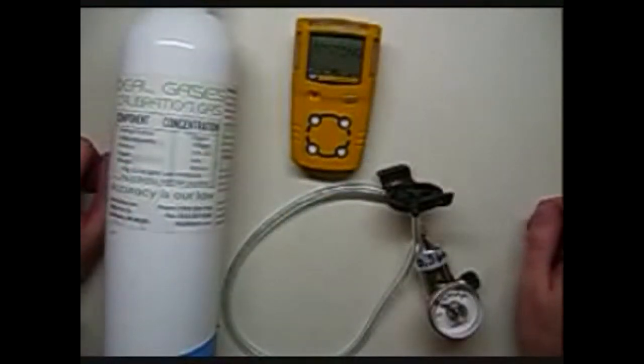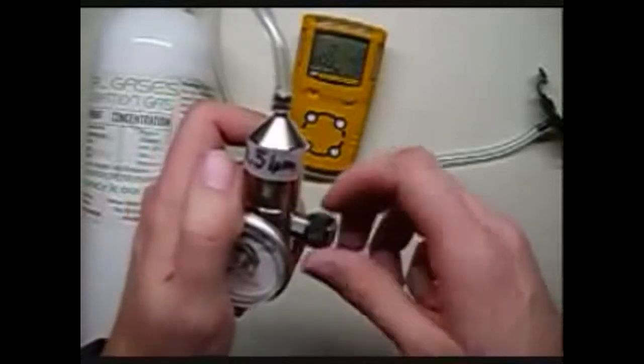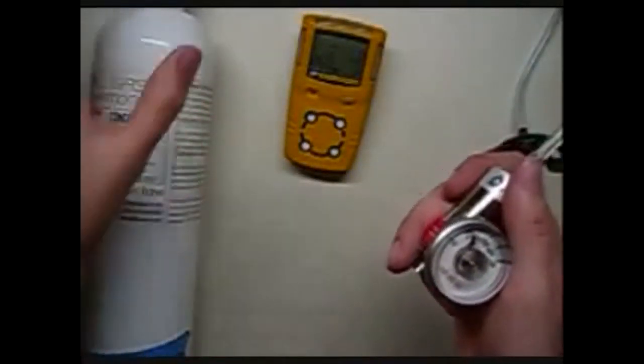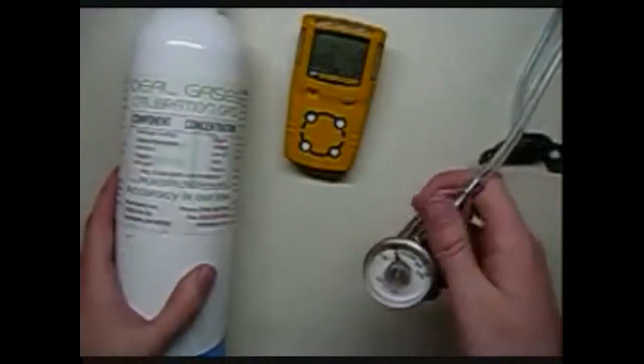The first thing you want to do to get the BW calibrated is attach your hose onto your regulator here. You want to open the regulator to make sure you're not putting a closed regulator onto a calibration gas cylinder. The last thing you want to do is have a closed regulator on a cylinder, as it can impair the quality of your gas.